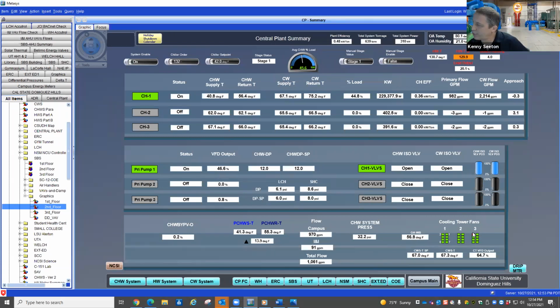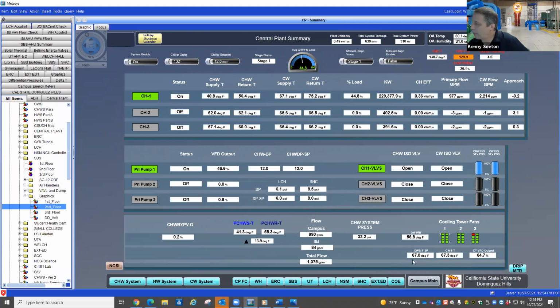Our cooling towers, we have 3 large cooling towers. Each one has 8 fans. You see that one of those 24 fans is actually offline right now. After the open house, we're going to replace it. The cooling tower water is 67 degrees, and the towers are running at 64%. So we're doing pretty good there. We can see how much water we're pumping throughout the campus. Right now we're pumping 1,000 gallons per minute through all those pipes that we went through in the tunnel system. We have one pump doing all that work and it's at 46%.